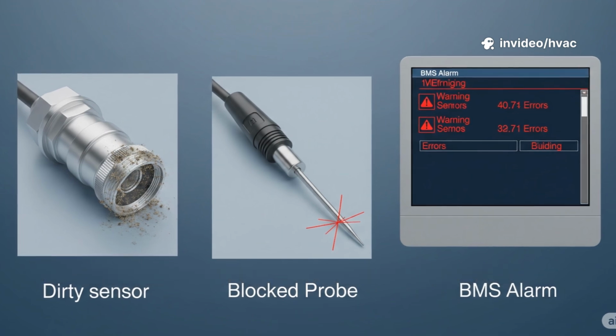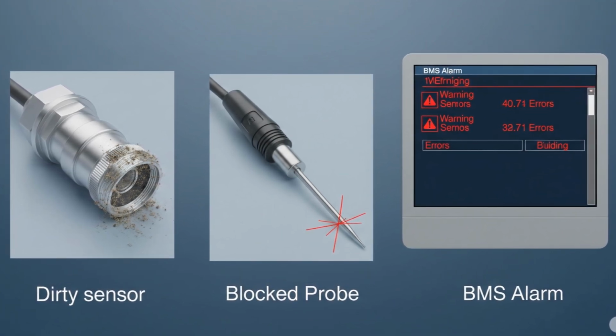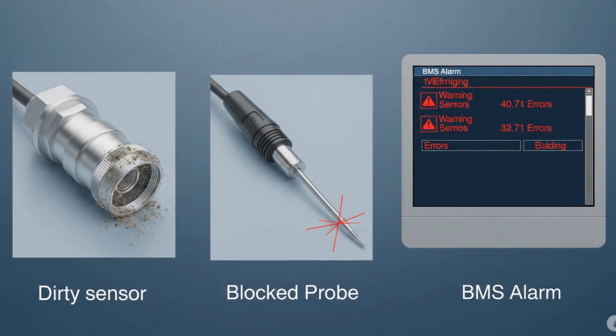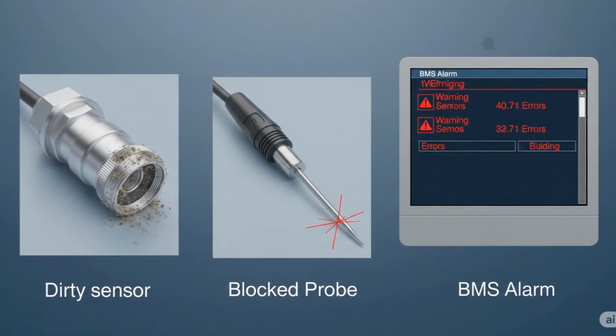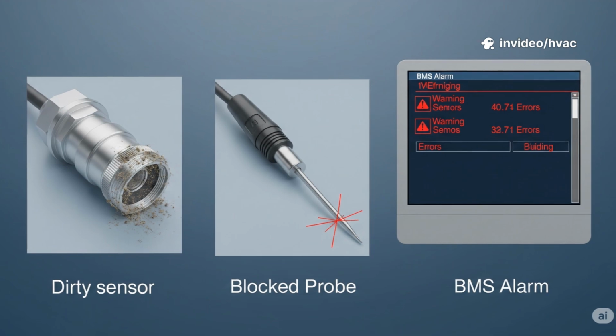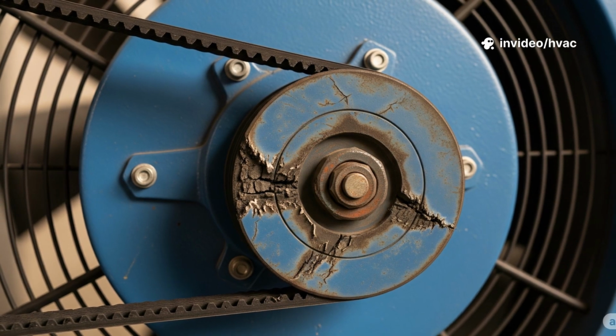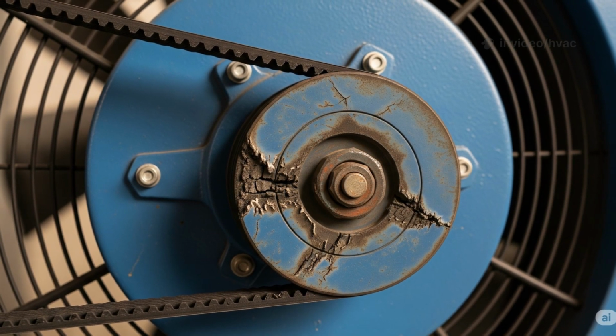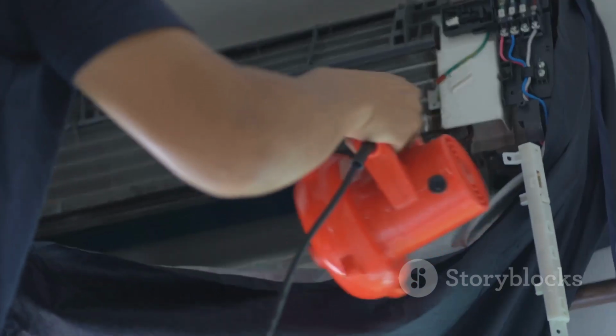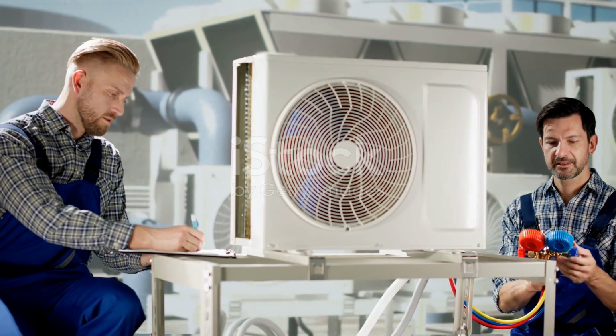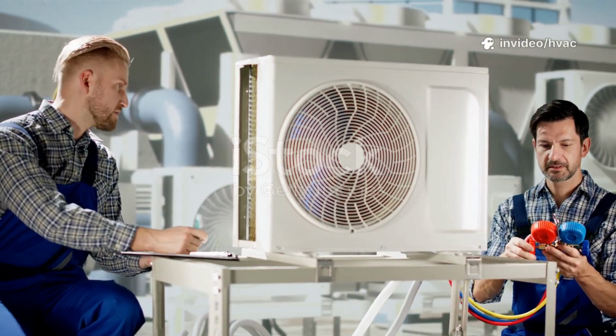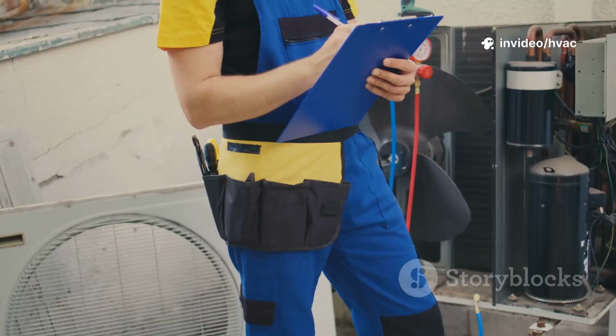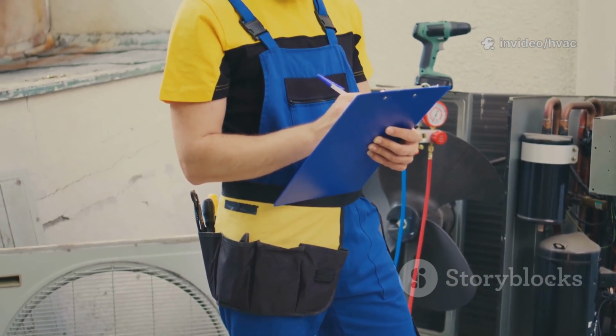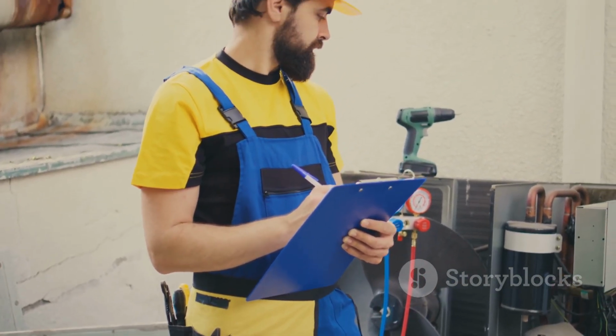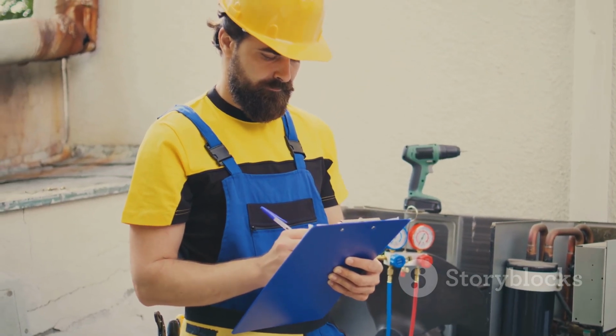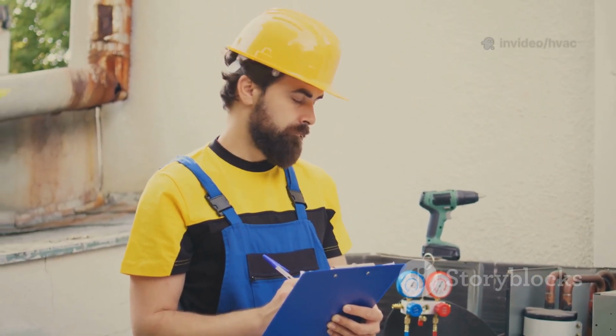Common airflow measuring station problems include things like clogged sensors, incorrect installation, signal drift, or even broken cables. Alarms might pop up if there's an airflow drop, which could be caused by filter clogging or maybe a fan belt issue. So it's important to train your maintenance team to spot unusual trends, inspect probes, and clean them on a regular schedule. Regular calibration of sensors is also crucial to maintain accuracy and prevent false readings. Always keep detailed maintenance records and refer to manufacturer guidelines for troubleshooting. If persistent issues occur, check for wiring faults or consider replacing faulty components.